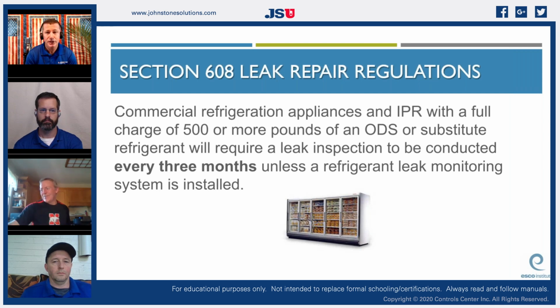So every grocery store in the United States that has 500 pounds or more of refrigerant in it is required for that entire store to have a leak inspection every quarter. So every quarter I went to every one of my stores and I did an entire store leak inspection. Usually it took a day, sometimes 2. Wow. Yeah.